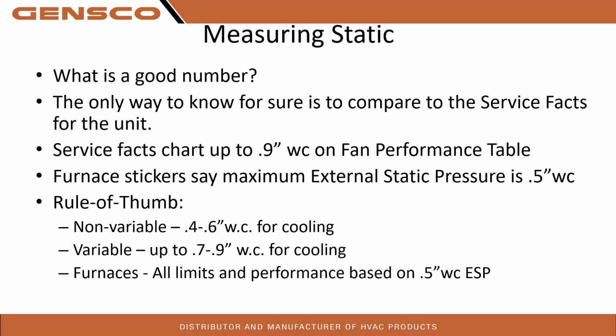So measuring static, what is a good number? What is a good number that you should see when measuring static to confirm you've got a good system? The only way to know for sure is to compare to the service facts for the unit. Service facts chart up to 0.9. This is important on the fan performance table. So if we start seeing over an inch, like a 1.2, we're off the charts. So keep that in mind. Anything over an inch on the communicating air handlers and whatnot, they will give you a static pressure alert.